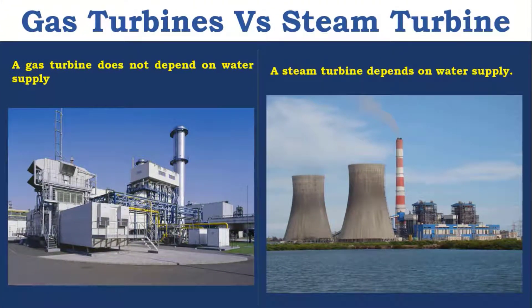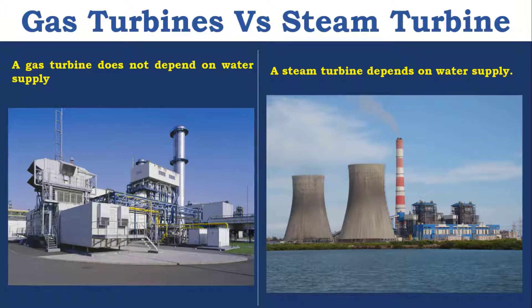The Gas Turbine does not depend on water supply, because we do not need to cool anything and the working medium is Gas. Whereas Steam Turbine depends on water supply. If you go for an open system, we need to replace water continuously to the boiler. If it is a closed system, we have a condenser, and to cool the condenser, we need water. That's why Steam Turbine depends on water supply, whereas Gas Turbine does not.